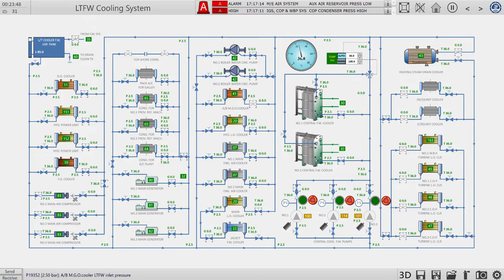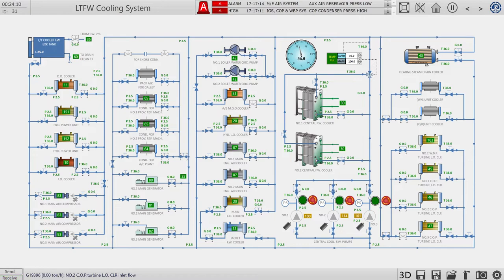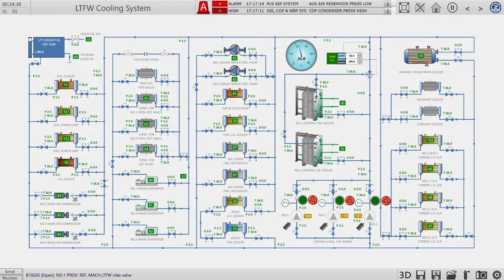All water starts to circulate. Also the workshop unit cooler and the turbine cooler — it is really good to circulate water through the entire system. Since our vessel is new and on delivery, all chemicals will circulate through the lines and keep them in good shape. If valves are closed for one or two years without operating the equipment, the water will form sediments or local corrosion will be initiated. All inlet and outlet valves are now open and our cooling system is ready.